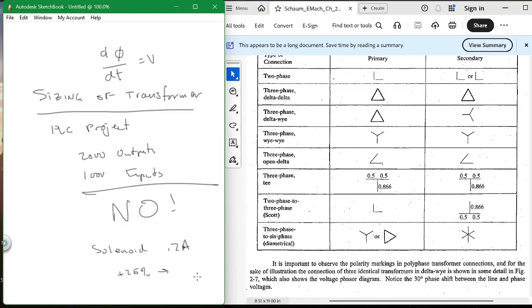I've seen people put huge transformers on panels, set them right on top, when they don't need that much. The reason is they sized based on the maximum output of each device. Don't do that, because it's about 2 to 3 times what your actual running value is.